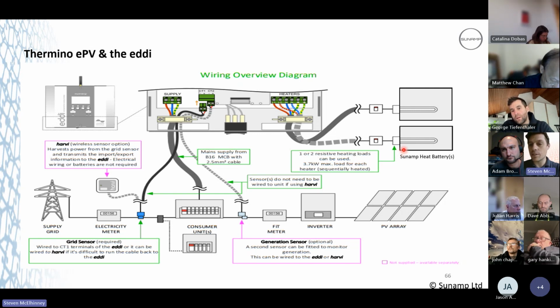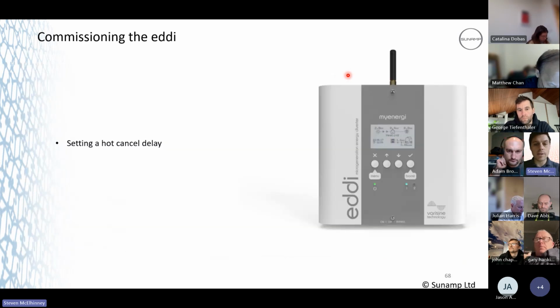It's a flow of electricity, and if you've got a flow of electricity, the eddi recognises that. When you're up to temperature, that flow stops, and then it thinks maximum temperature reached and flicks over to the second one. There's a very important thing with that as well, which we'll cover during the commission: setting a hot cancel delay.